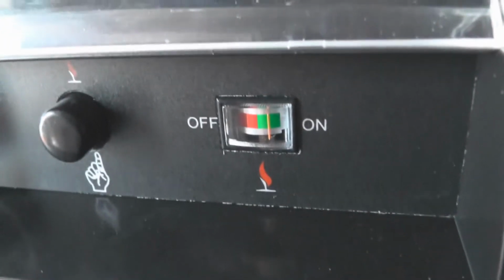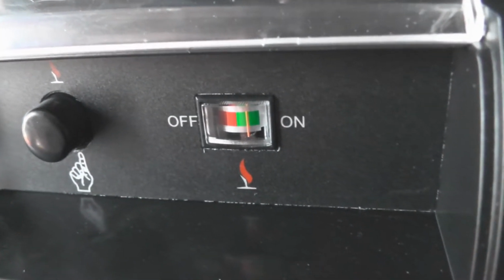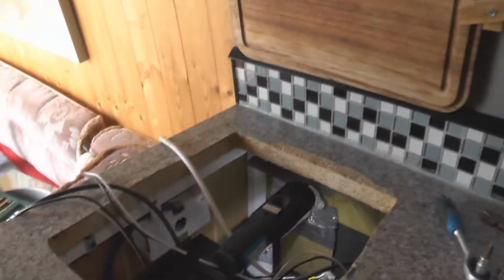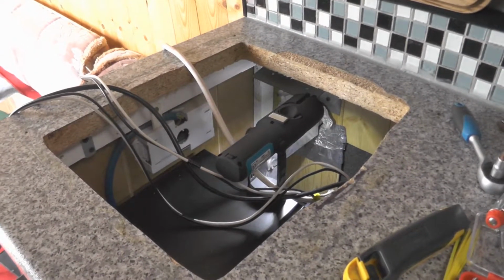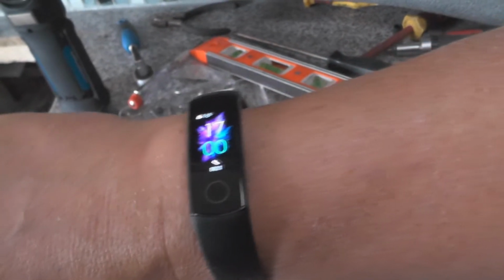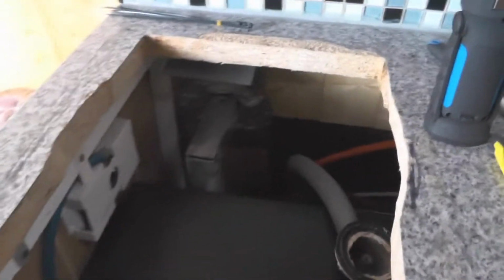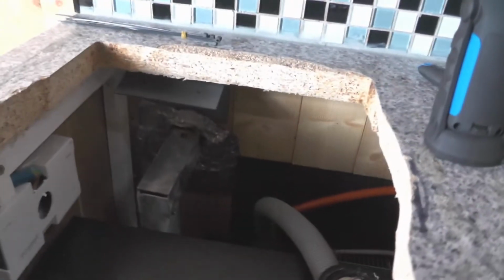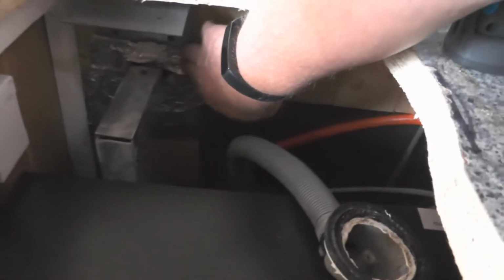As you can see there, it's showing gas is on, happy, working fine. And we'll just check that it gets cool with the gas as well. Okay, 2 hours that's been on now, or more than. Heat coming from the flue there, not massive amounts of heat either, just enough. No damage to the back there, nothing scorched, so basically yeah, I'm happy.